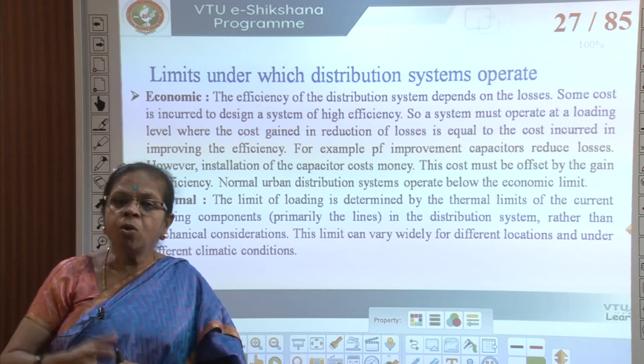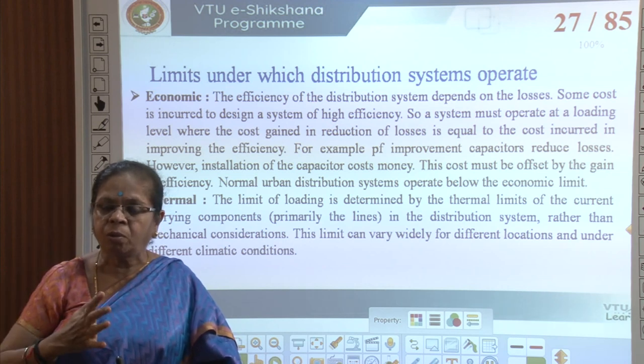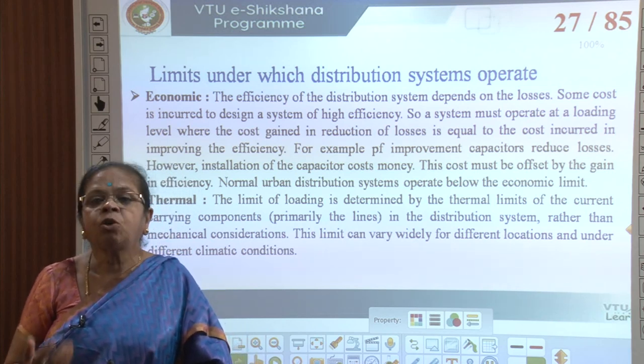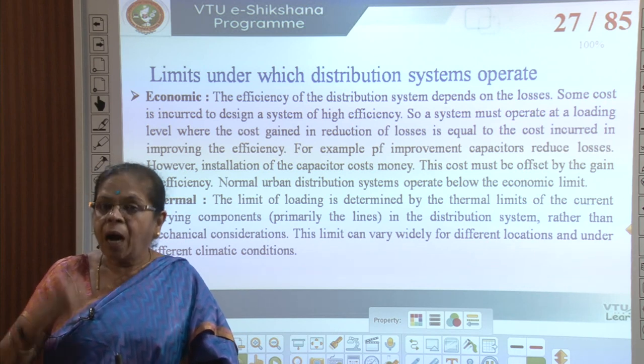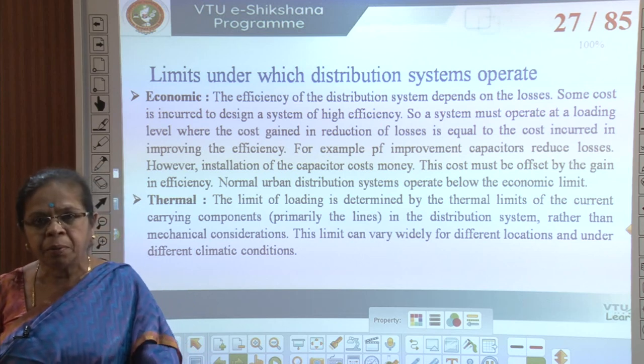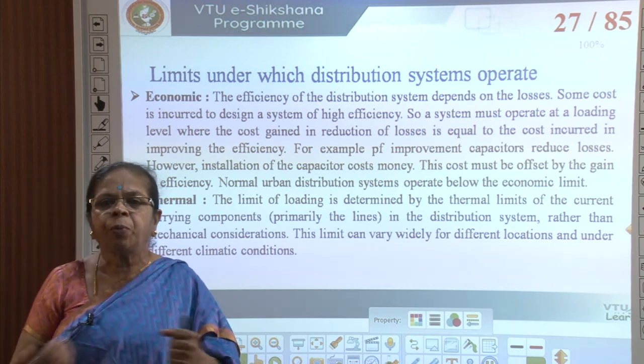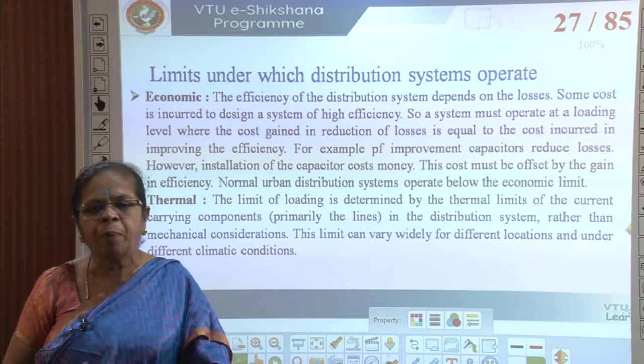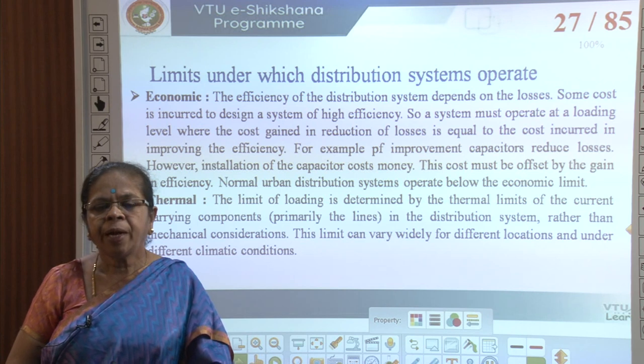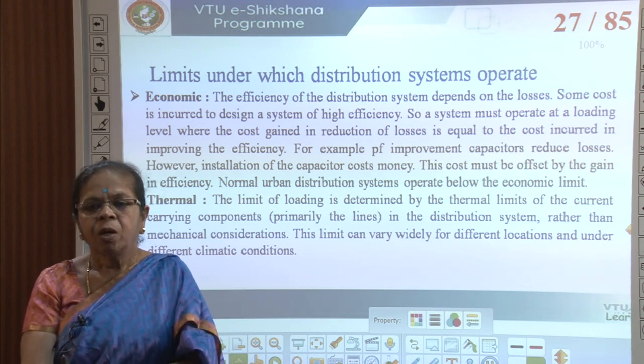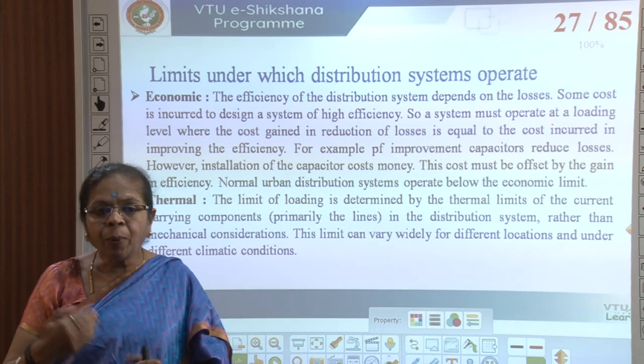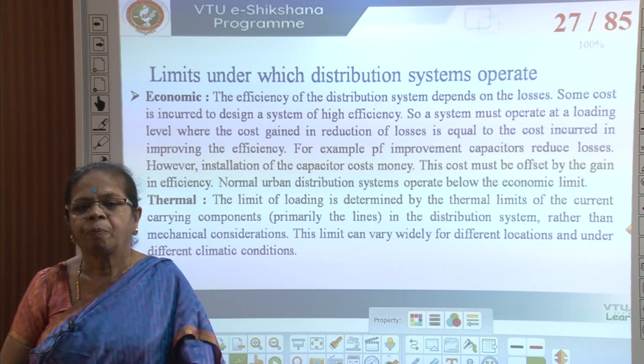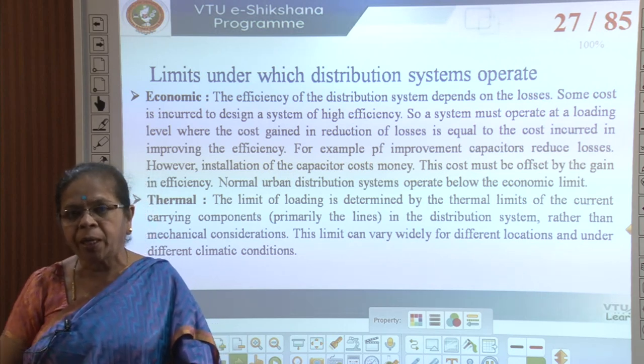To increase efficiency I have to reduce losses, and to reduce losses I have to take certain measures that cost money. If I improve efficiency I save some money, so I operate at a point of equilibrium between these two. For example, to reduce losses I improve the power factor by putting in power factor capacitors. Installing a power factor capacitor costs money, so this cost must offset whatever gain I get by improving efficiency; otherwise I spend more money than I get. Generally, urban distribution systems operate below the economic limit.